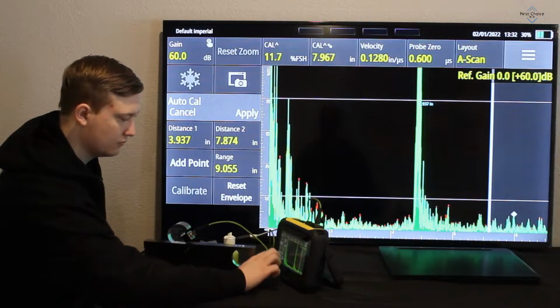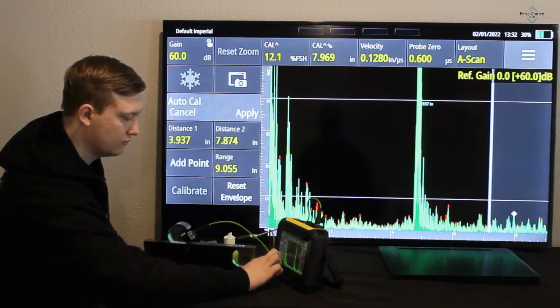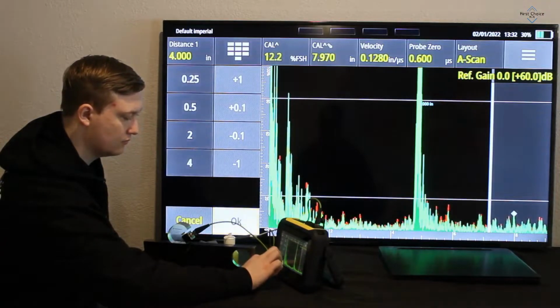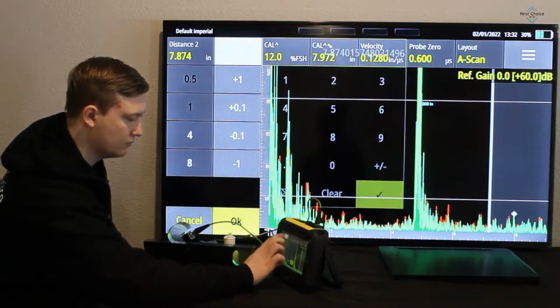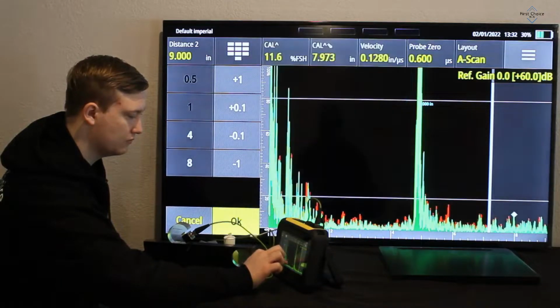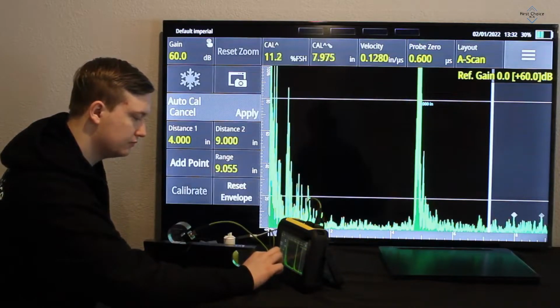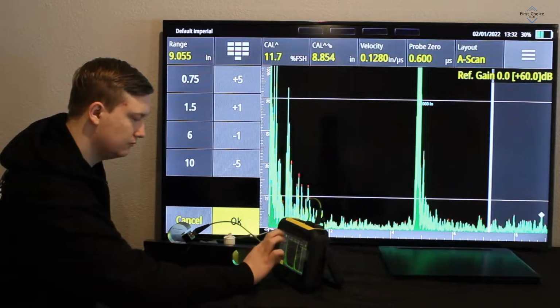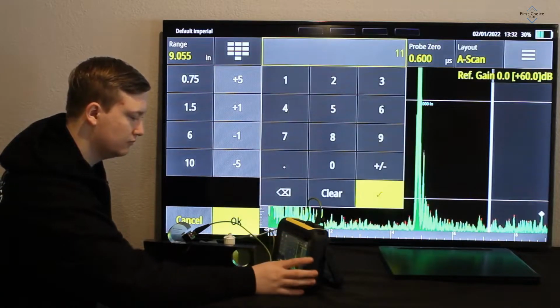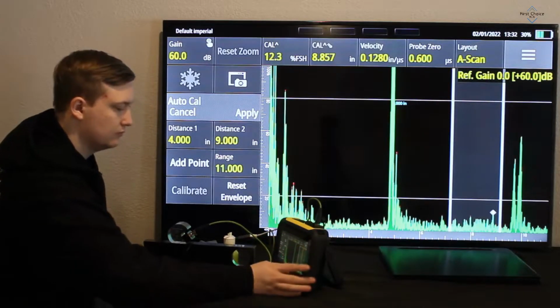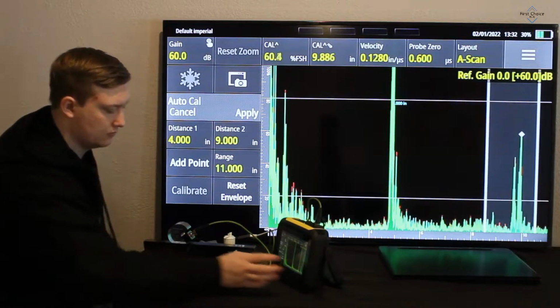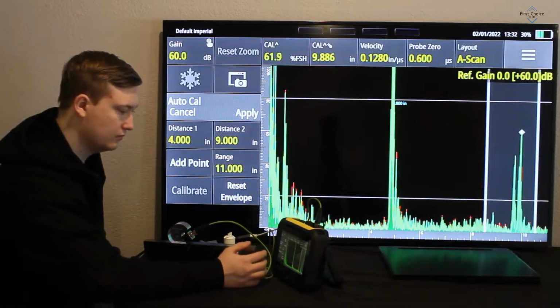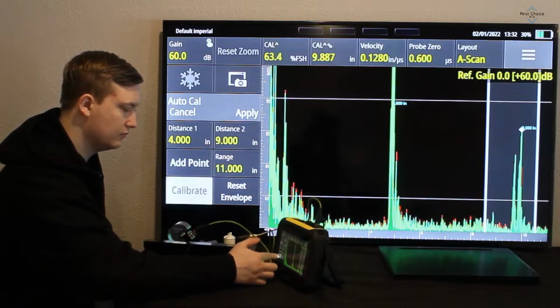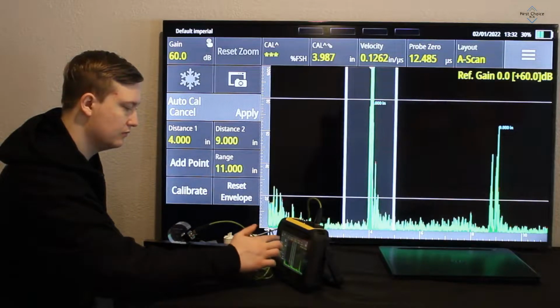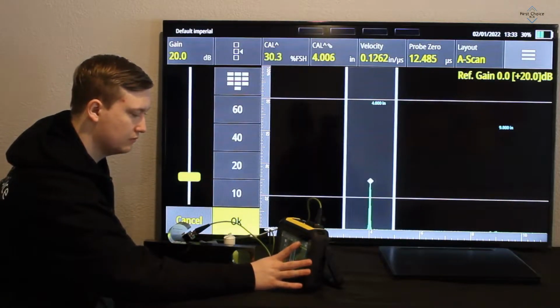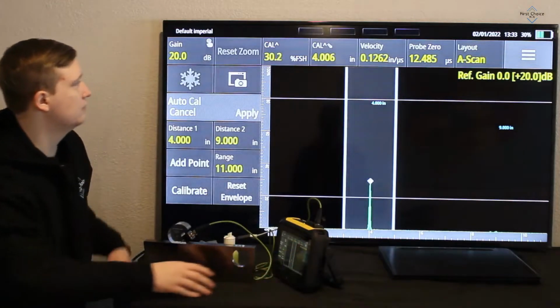You have to change the distance 1 and the distance 2 mark as well, so I'll change that to 4 and 9. Here that goes. So 4, 9, and I'll also increase the range to 11. Because when the machine is not calibrated, it will not be on the 9 mark, and you will not see the back signal as you see right here. It is around the 10 mark rather than the 9. So if I had it on a 9-inch range, I would not be able to see that last signal.